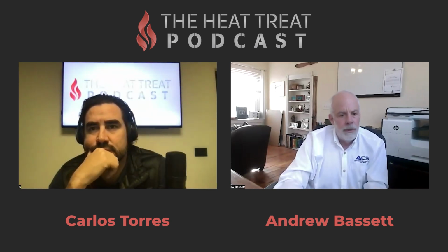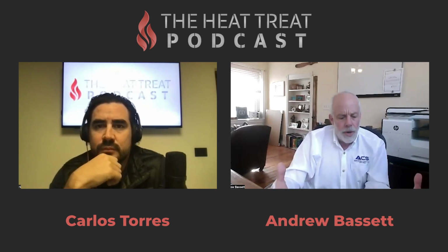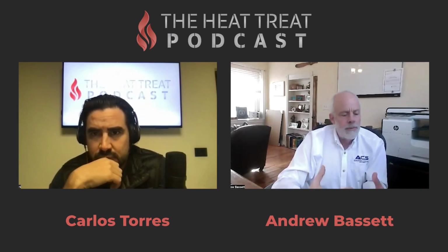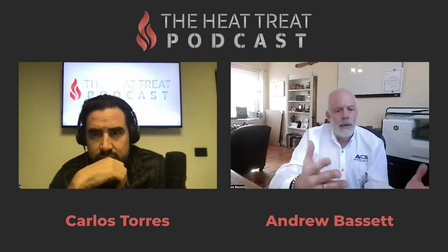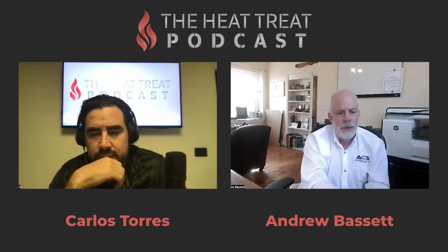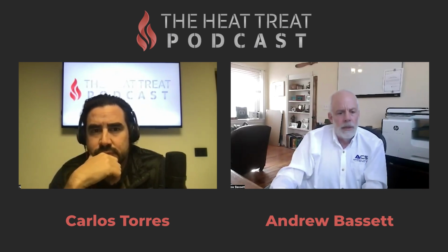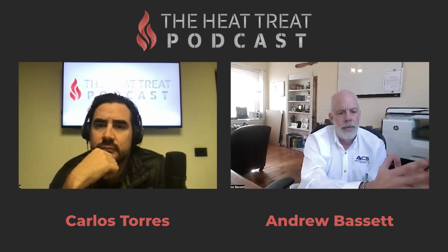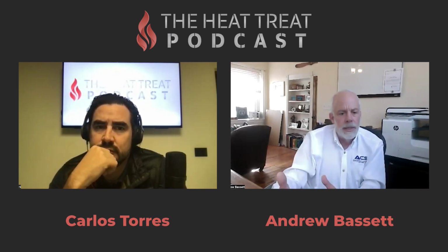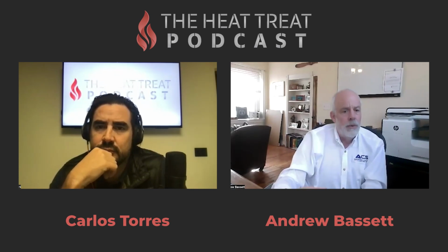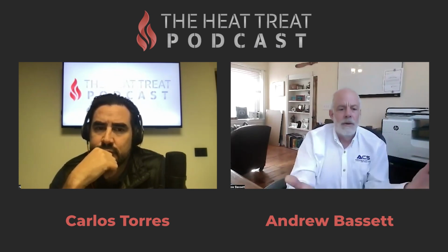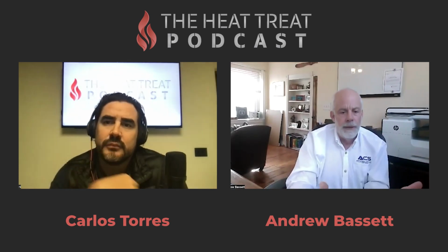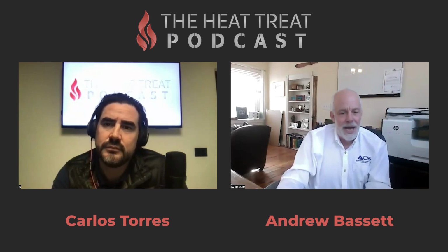I think a lot of people dealing in thermal processing, especially new people, say 'you calibrated my instrument, it said 400 degrees, but it's not really 400 degrees because my parts are overbaking.' Well, yeah, that's one aspect - we make sure the instrument's correct, but the rest of the system could be wrong. It's like your oven at home - you set it for 350 to bake a pie, people think it's actually 350, but...